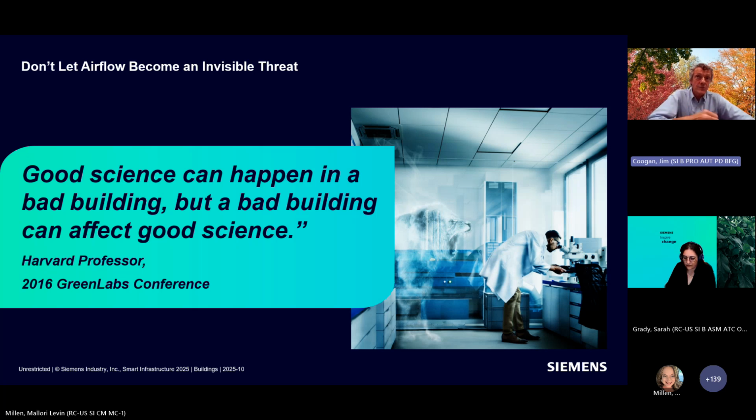In terms of contaminant sensing, you have similar issues. Am I sensing the contaminant of concern? There's a good chance that they're using some stuff that we don't have sensors for. There's a real good chance of that. Am I sensing at the level of concern? Are the sensors I have sensitive enough for what the hazard is? And finally, are we sensing at the point of exposure? Probably the answer to all three of those is no, okay? Probably the answer to all three is no.